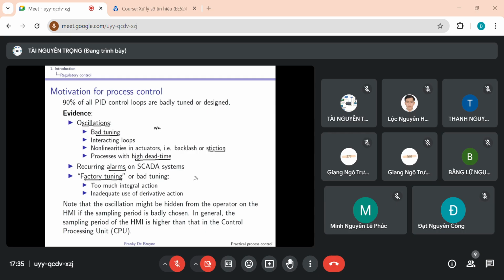Factory tuning is, for instance, if you take a PID controller from the library, it might be that it comes with those parameters here: KC is equal to 1, TI is equal to 10 seconds, and TD, derivative action, is equal to 0. We'll see later why this is chosen as factory tuning. But if you see on your faceplate that your controller has this original factory tuning, there is a big chance that nobody has ever looked at the tuning on that controller, and that it is a good candidate to start the tuning exercise.